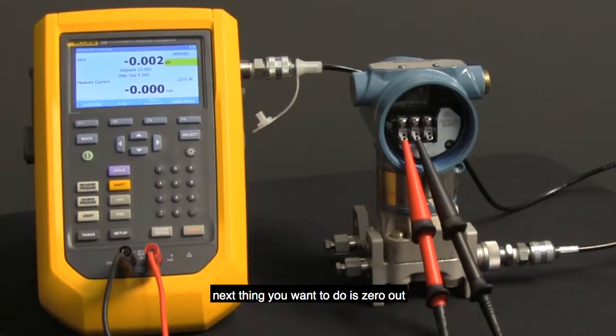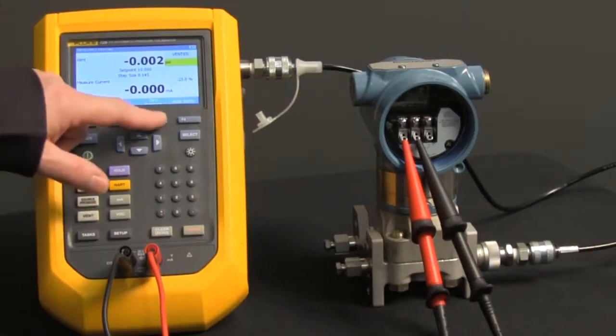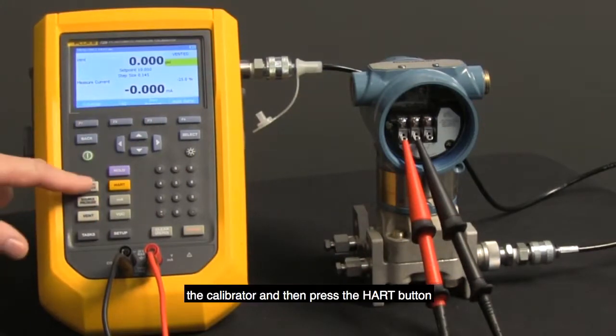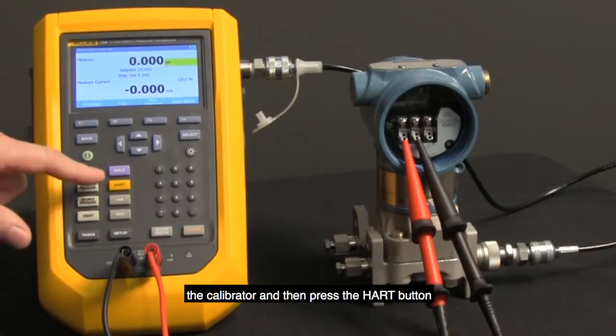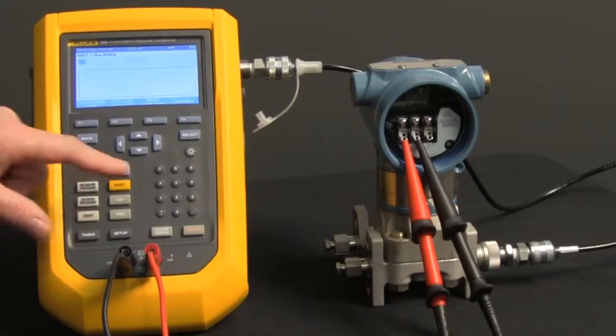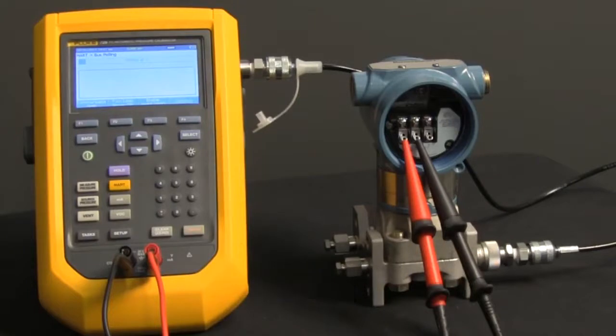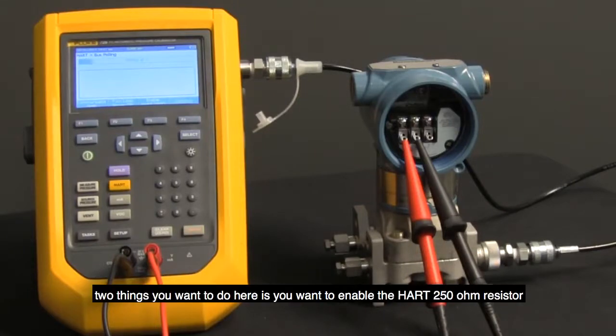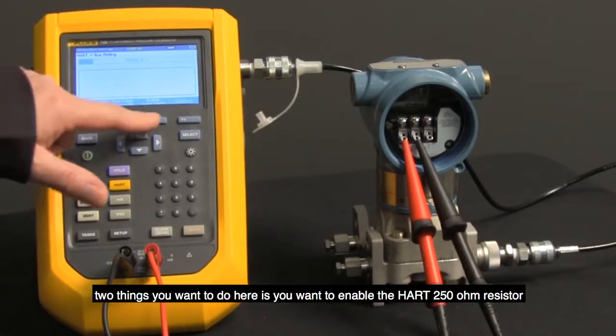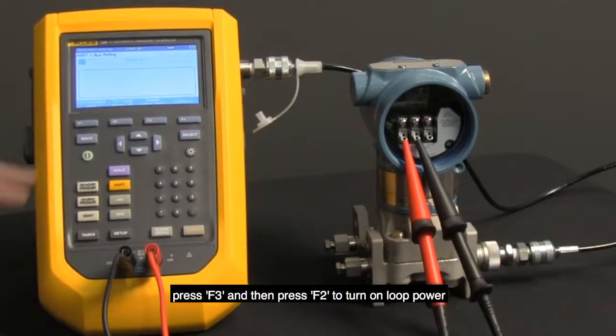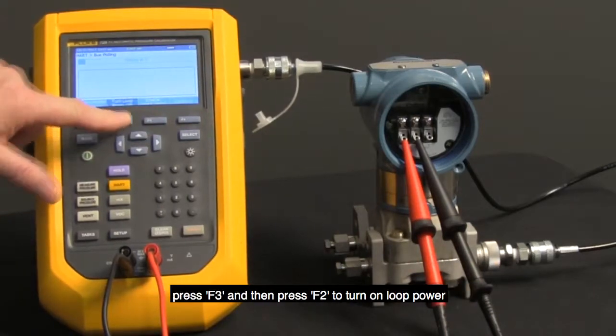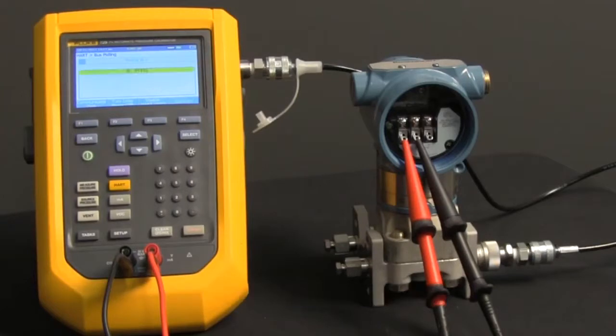Next thing you want to do is zero out the calibrator and then press the HART button to set things up. Two things you want to do here: enable the HART 250 ohm resistor, press F3, and then press F2 to turn on loop power.